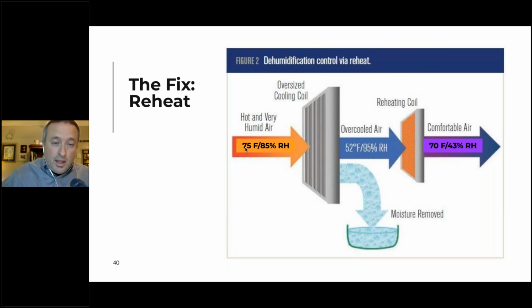So here's what happens. We have that 75-degree, very humid air going into the air conditioner coil, and then it gets cooled off. So now it's cold and dry. 95% may not look dry, but that's like the 50-degree dew point. That's quite dry.